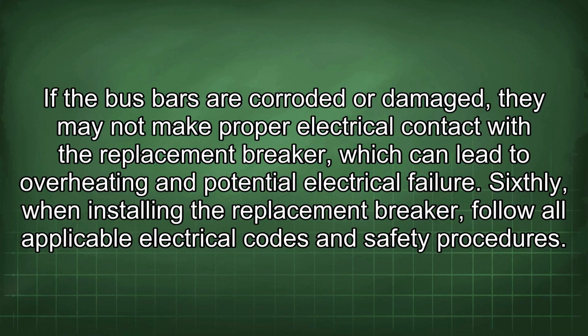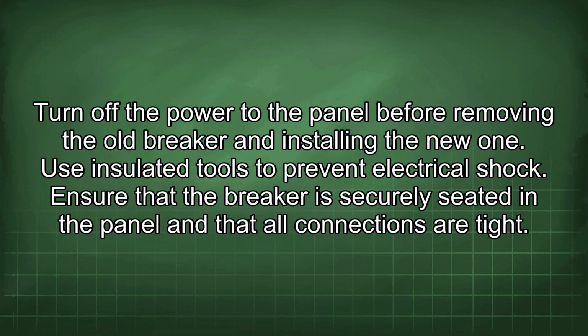Sixthly, when installing the replacement breaker, follow all applicable electrical codes and safety procedures. Turn off the power to the panel before removing the old breaker and installing the new one. Use insulated tools to prevent electrical shock. Ensure that the breaker is securely seated in the panel and that all connections are tight.